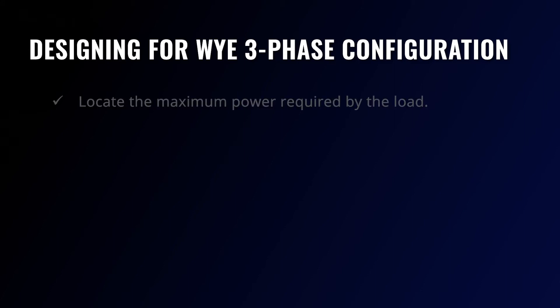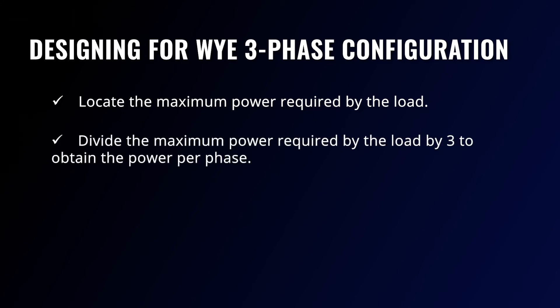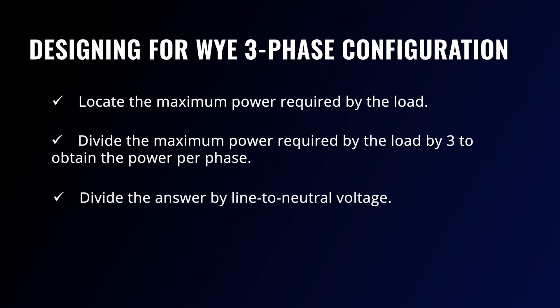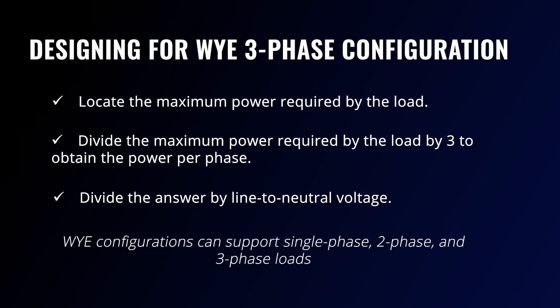As opposed to delta, this configuration can be used as a four-wire circuit or a five-wire circuit. Y configurations are generally used in power distribution networks and are primarily required in applications that call for fewer starting currents and travel longer distances. To design for the Y three-phase EMI filter, you must locate the maximum power required by the load, divide it by three to obtain the power per phase, and divide the answer by the line-to-neutral voltage. Y configurations are preferred for power distribution because they can support single-phase, two-phase, and three-phase loads.